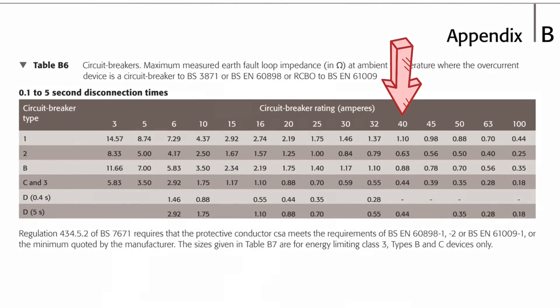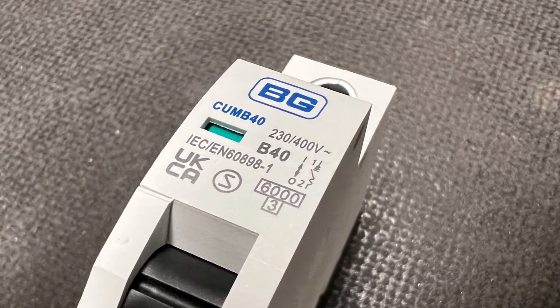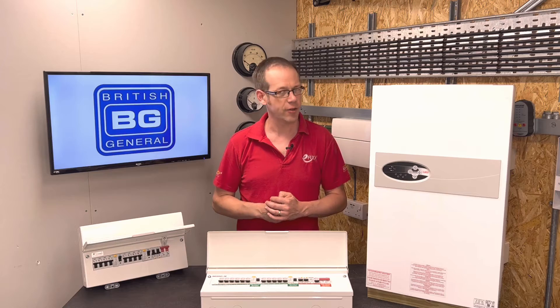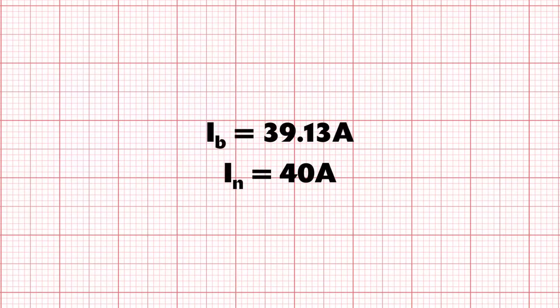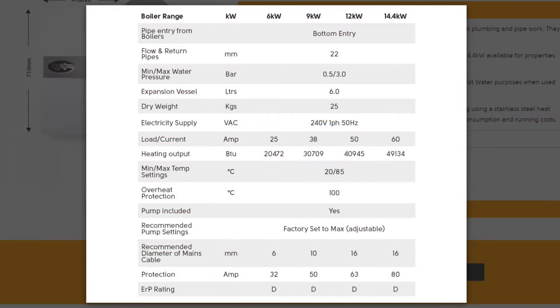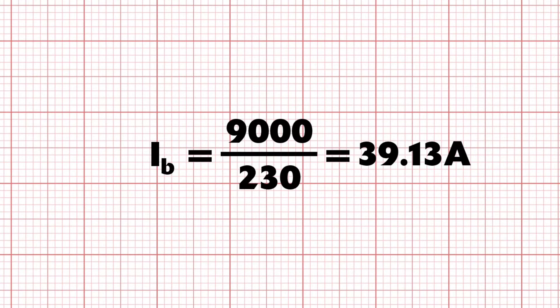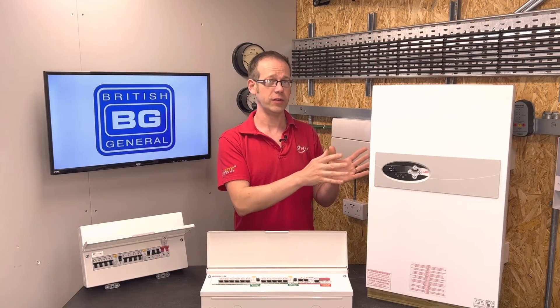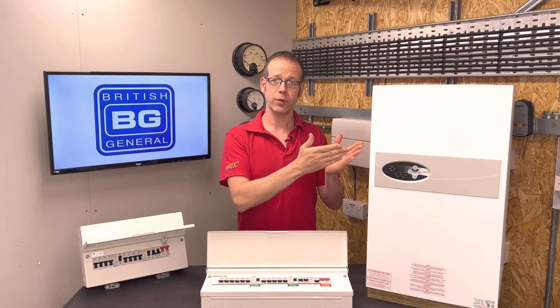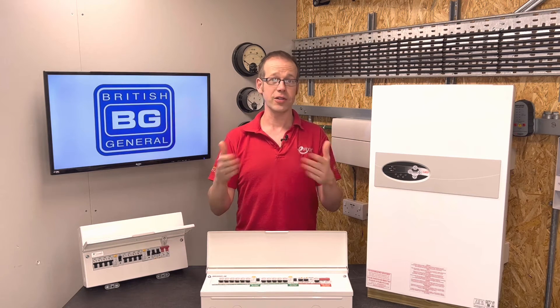At this point we'll go on a quick side quest to discuss an interesting point. You'll notice the design current is very close to the nominal rating of the circuit breaker, which in theory isn't really a problem. However, if you look at the technical data for this boiler, you can see that the recommendation is that it's protected by a 50 amp MCB. Why the suggestion to go up to this larger size? It's because we calculated the design current using the nominal voltage, which is correct — however, because the load is purely resistive, if the real-life voltage is higher than the nominal value it will cause more current to flow, potentially pushing it over 40 amps.